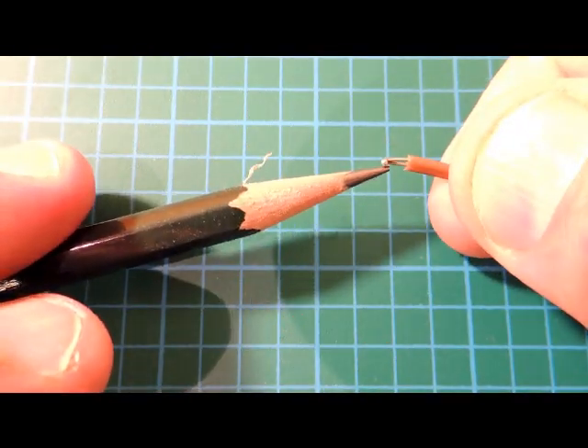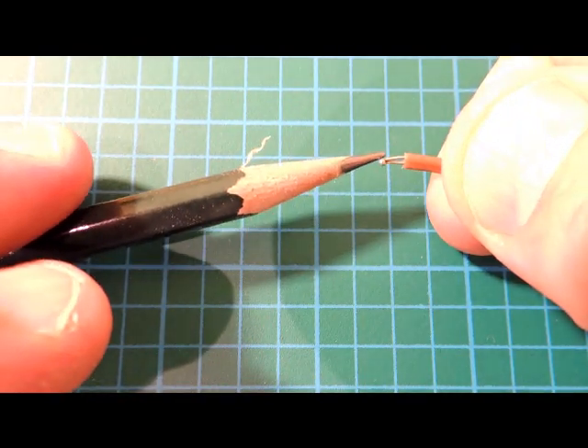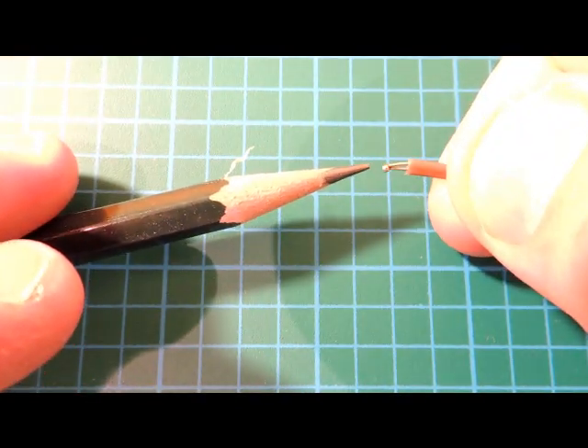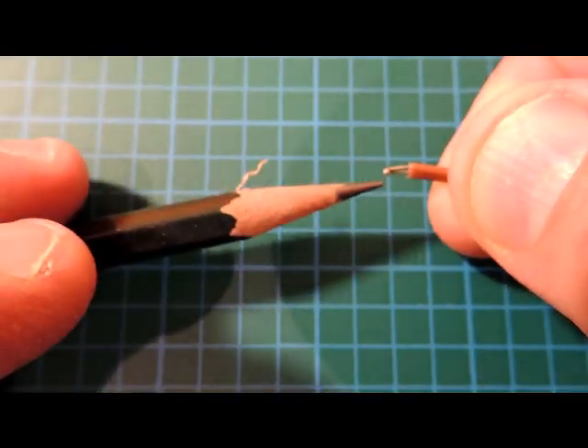The key feature of the thermocouple is its very small mass. You can see I have a little pencil here for comparison. That's important because if you're trying to measure rapid temperature changes, you don't want to be sucking energy in and out of your sensor.